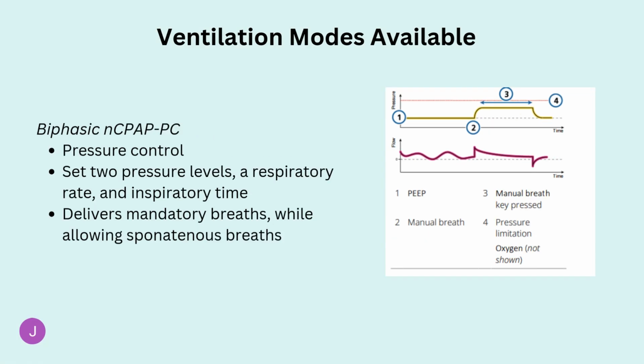In biphasic NCPAP pressure control, the clinician sets two pressure levels, a respiratory rate and the inspiratory time, and can adjust the flow as needed. This mode still allows the baby to take spontaneous breaths at both pressure levels while also delivering mandatory breaths.